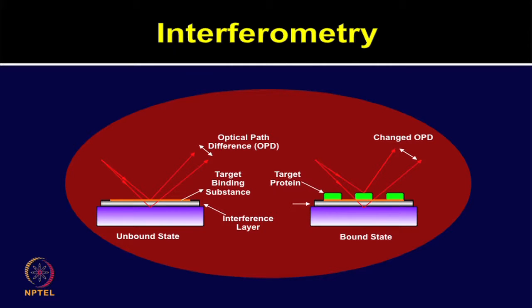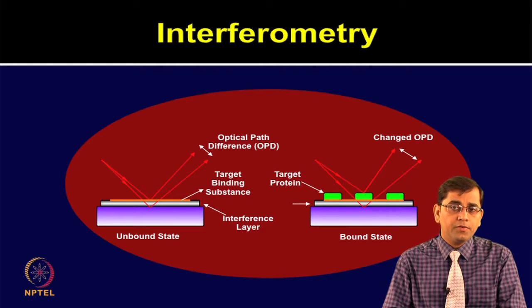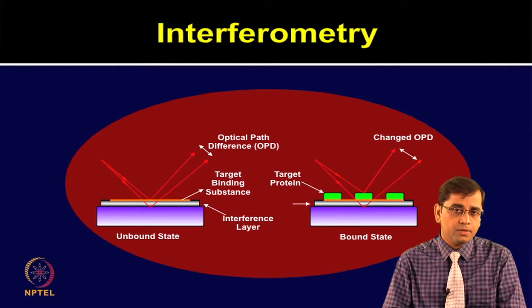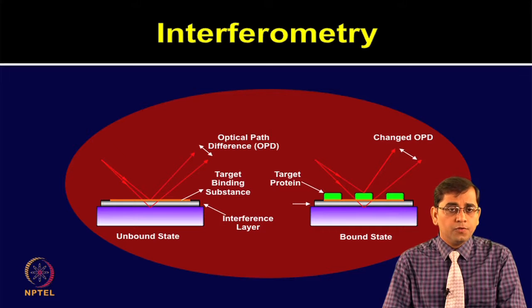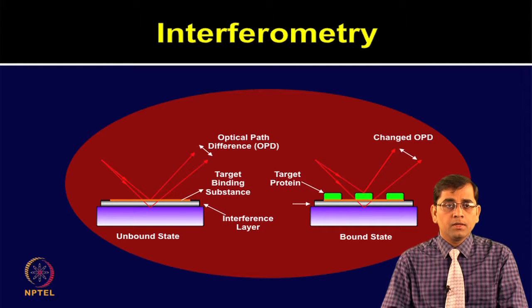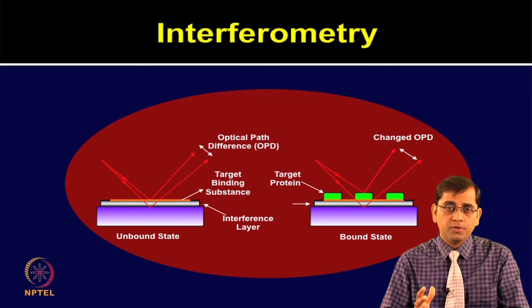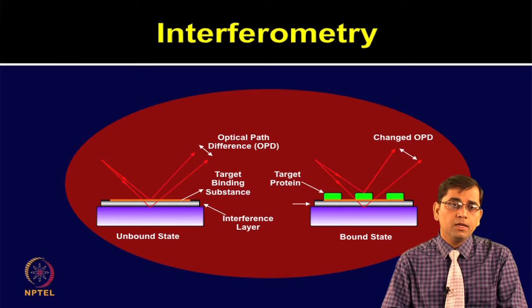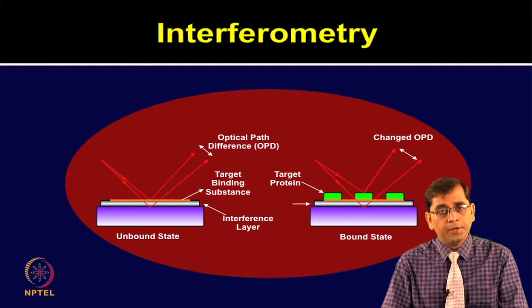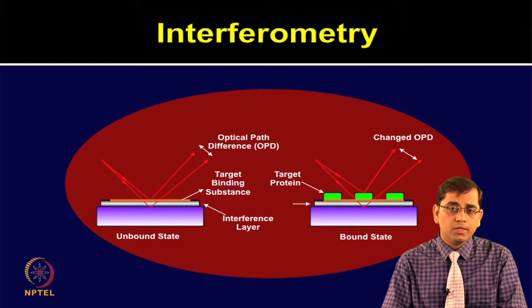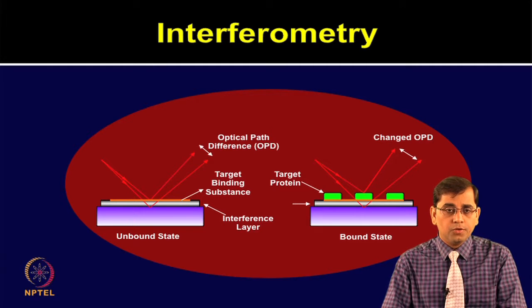Let us look at the interferometry principle in detail. In interferometry, the phase difference of wave fronts is transformed into observable intensity fluctuations, known as interference fringes. The interferometry techniques relate the optical phase to biomolecular layer density on the surface. The signal is created by an additional phase shift or optical path length difference caused by the adsorbate bio-layer. Biomolecules are printed on the surface; the left panel shows the unbound state, and the right panel shows the target protein bound state, where the optical path length difference due to protein binding is measured.